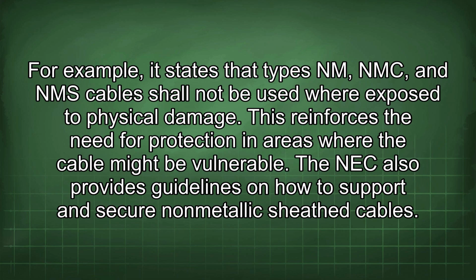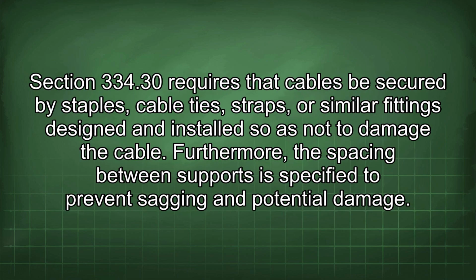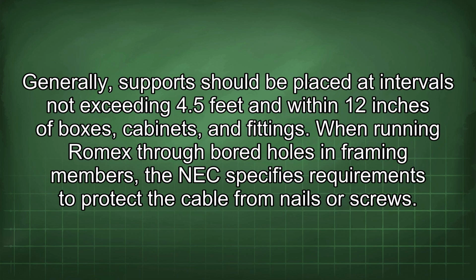The NEC also provides guidelines on how to support and secure non-metallic sheathed cables. Section 334.30 requires that cables be secured by staples, cable ties, straps, or similar fittings designed and installed so as not to damage the cable. Furthermore, the spacing between supports is specified to prevent sagging and potential damage. Generally, support should be placed at intervals not exceeding 4.5 feet and within 12 inches of boxes, cabinets, and fittings.